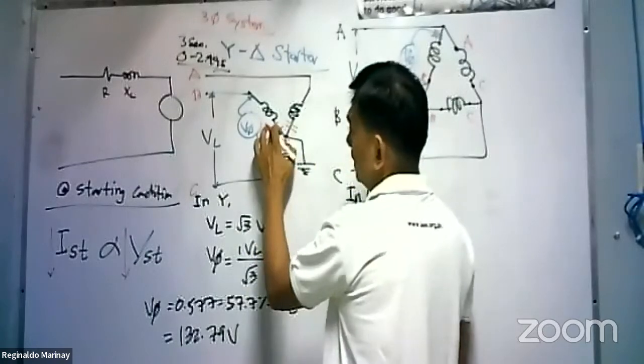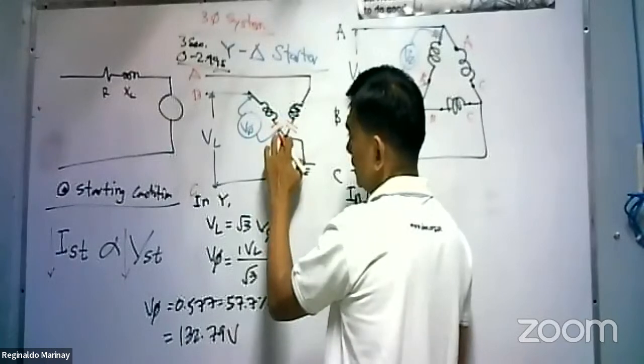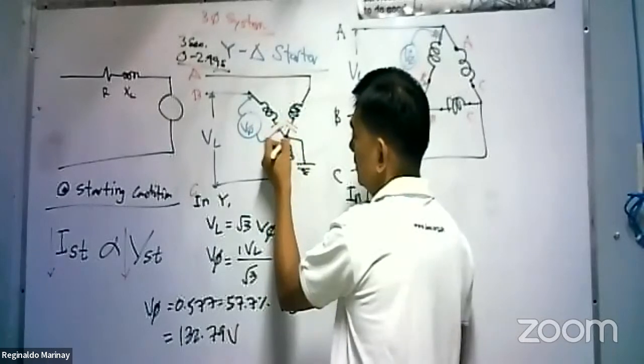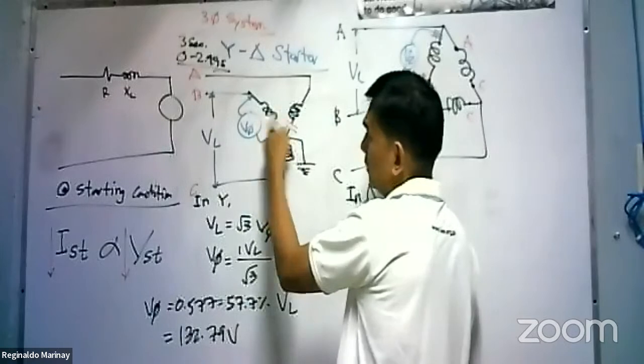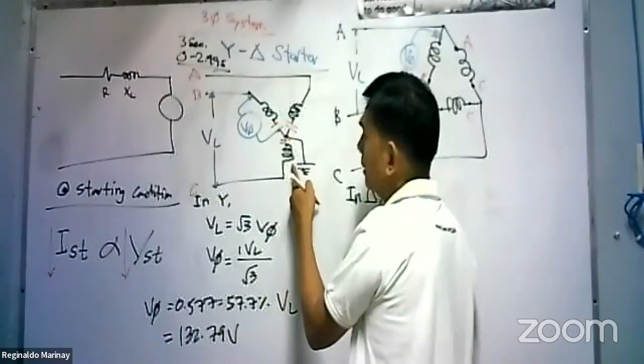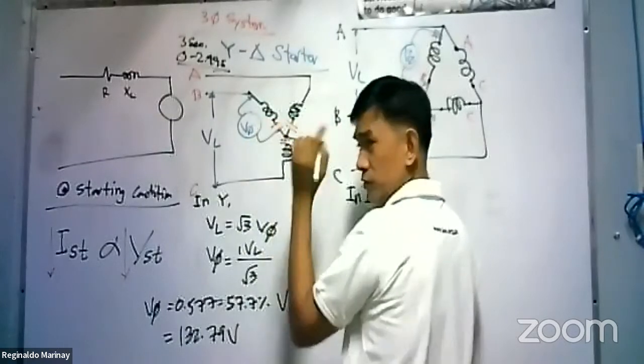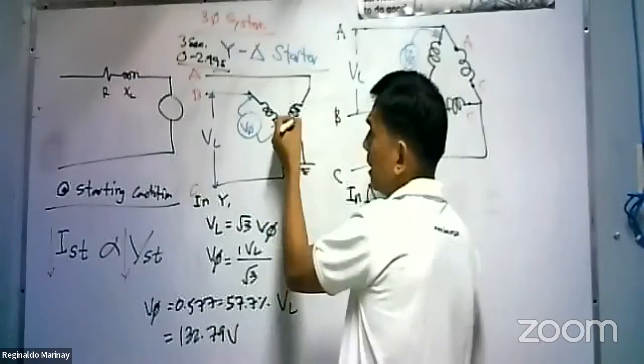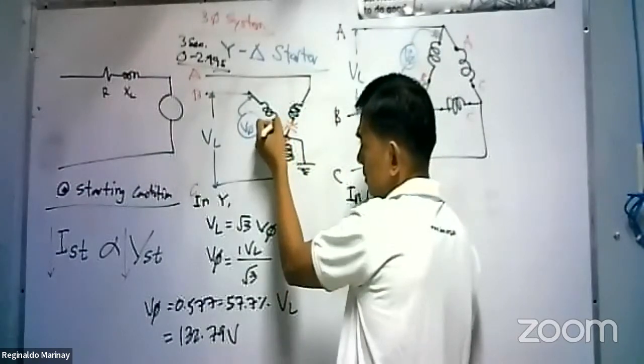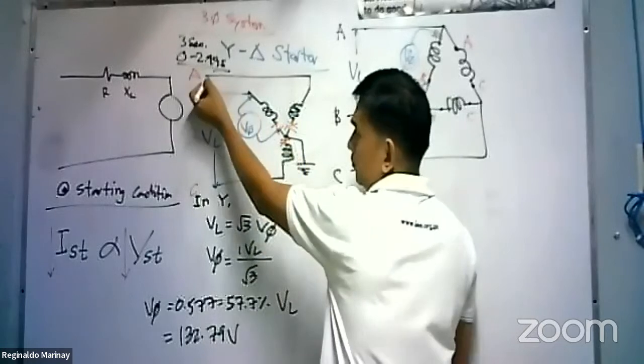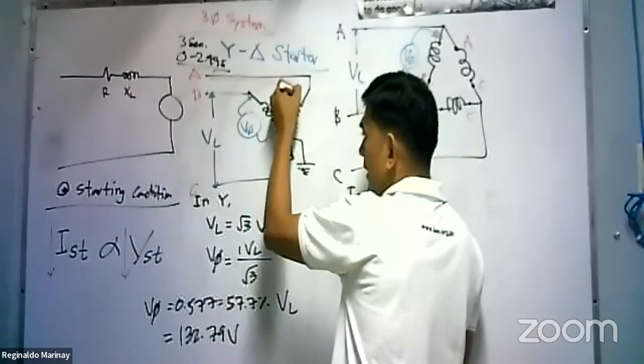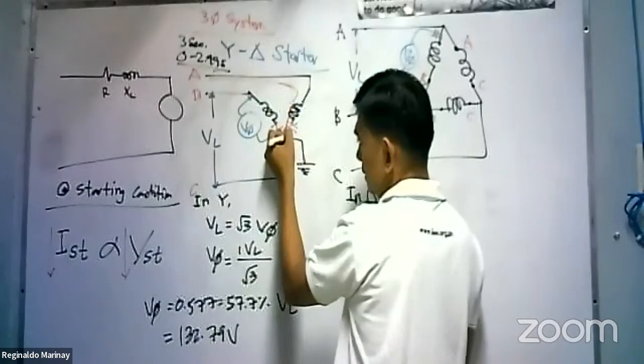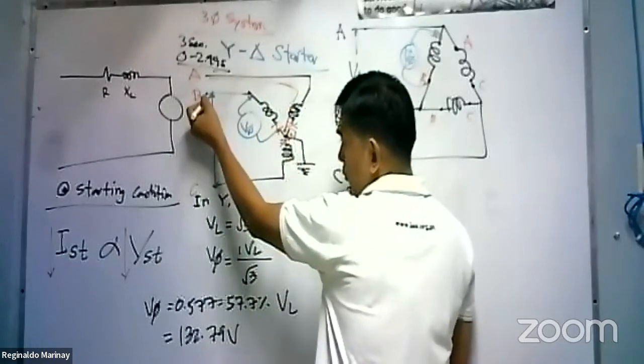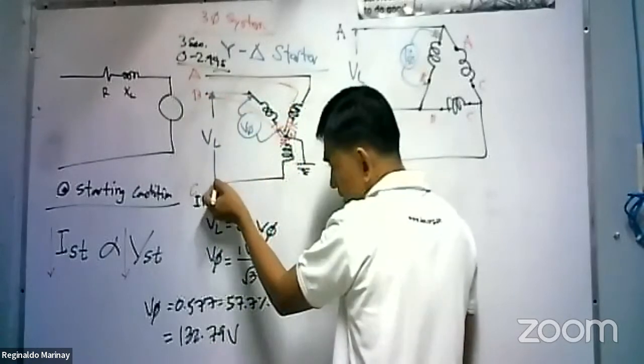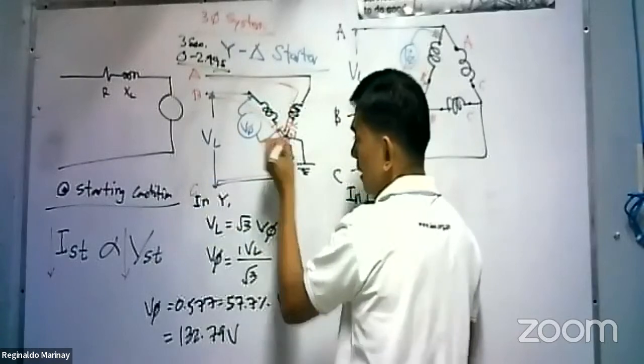Always remember that initially it is open circuited, right? These three windings are floating. But once we energize the timing relay, this will become closed. Then, of course, the current will flow here from line 1, from coil to the neutral. This is the neutral. From line 2 to the coil to neutral. Line 3, coil to the neutral. And also the same thing as this one.